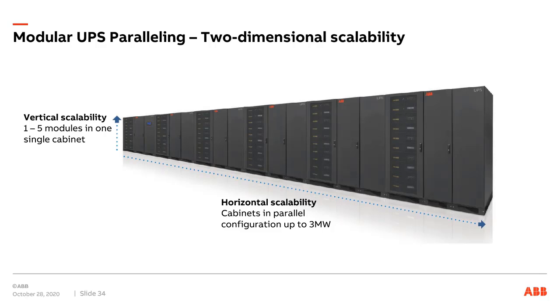They were starting out with 3, and as part of the factory acceptance test, they wanted to see the hot swap of the power modules. That was done on 2 units in parallel, supporting a megawatt, or close to 900 kW load, and then swapping modules without shutting down. And then the customer wanted to see how they could add a 3rd module, again without shutting down.